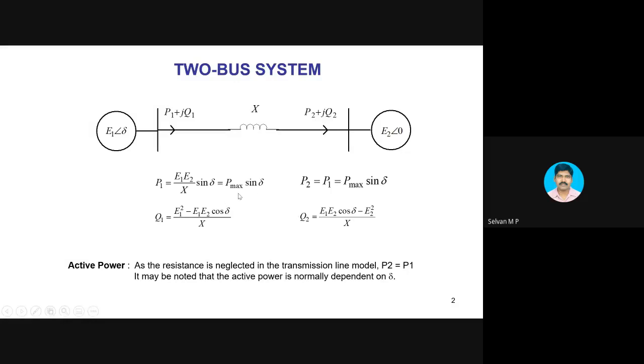P max will not change because I'm adjusting delta, because P max depends on E1, E2 and X, where delta is not there. So for a given transmission line, if you are operating at a given fixed voltage, then the maximum power that can be transferred is fixed. Whether we are achieving that maximum power or we are transferring less than that depends upon the angle at which you are operating. That is the capability of the machine. If I am able to operate at delta equal to 90 degree, then I will be able to transfer complete power. P max I can utilize, but it is never possible to operate at 90 degree because of the stability issues.